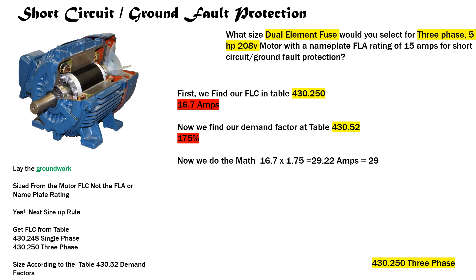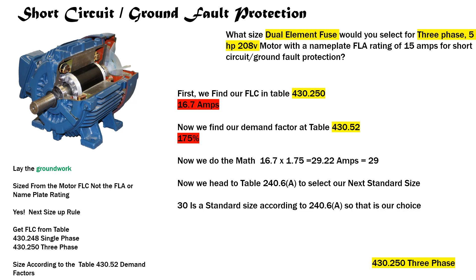We do the math: 16.7 multiplied by 1.75 gives us 29.22 amps. We drop it down to 29, then head to table 240.6(A) to find the next standard size overcurrent device — and we select 30 amps. That's our choice: a 30 amp dual element fuse, which is the first point of disconnect and short circuit ground fault protection for this motor.